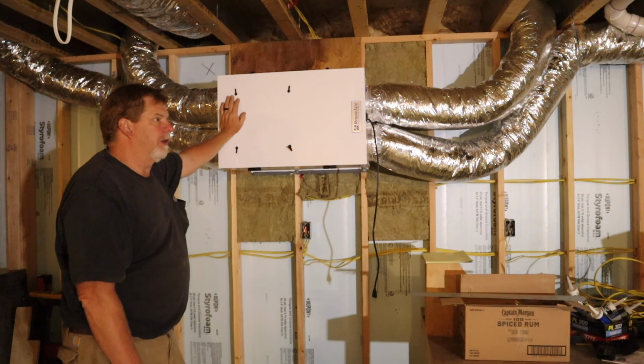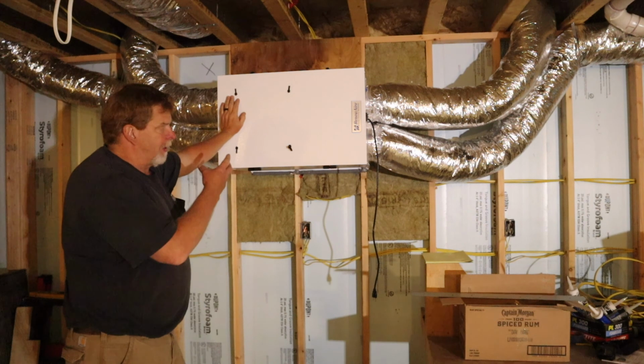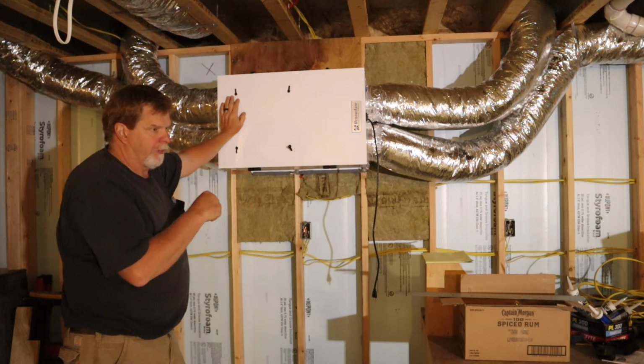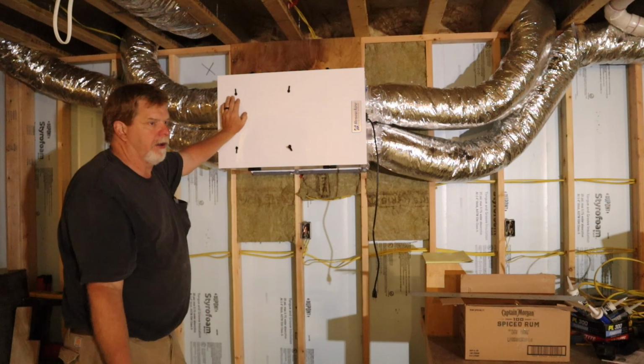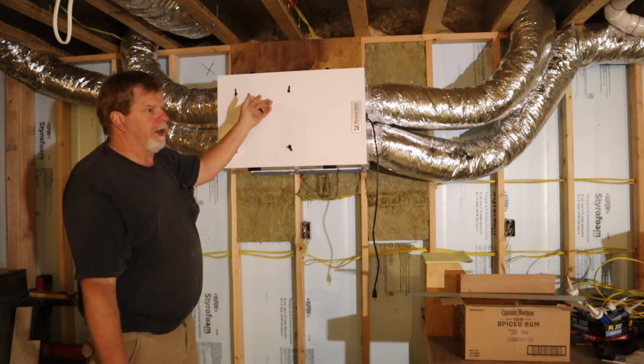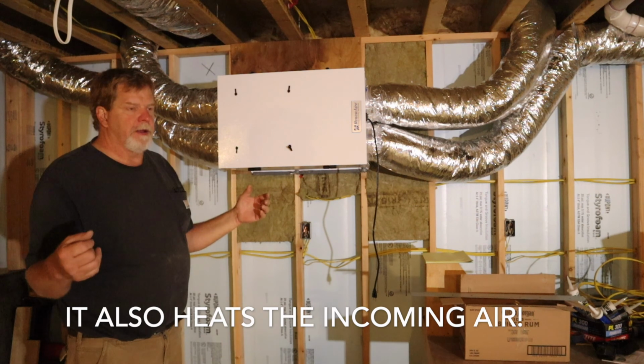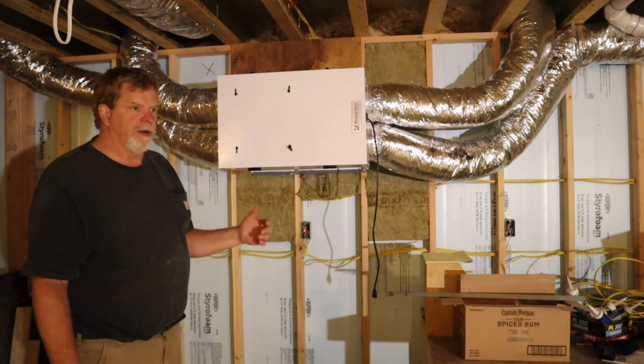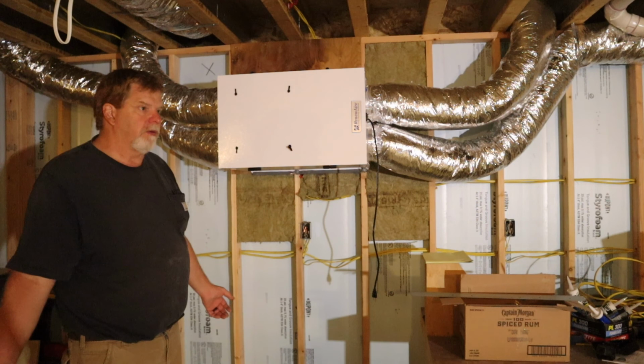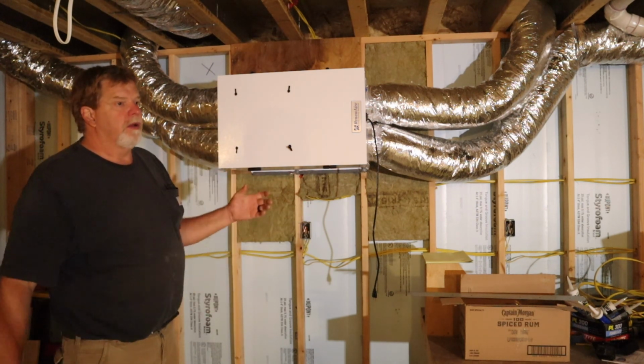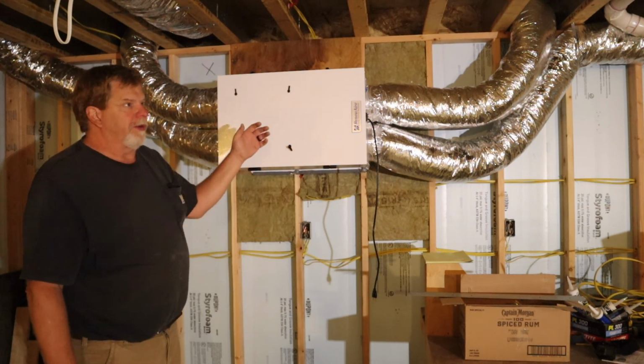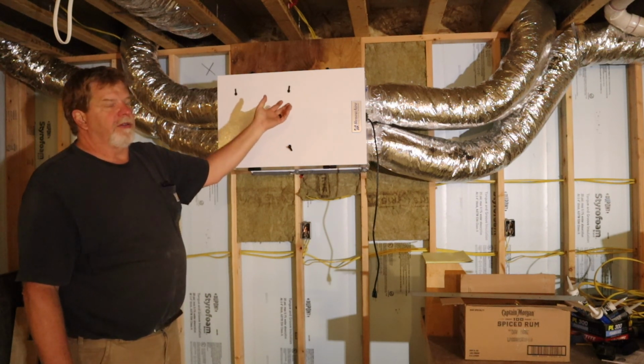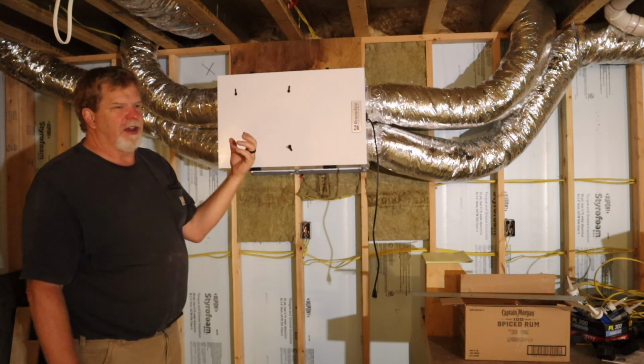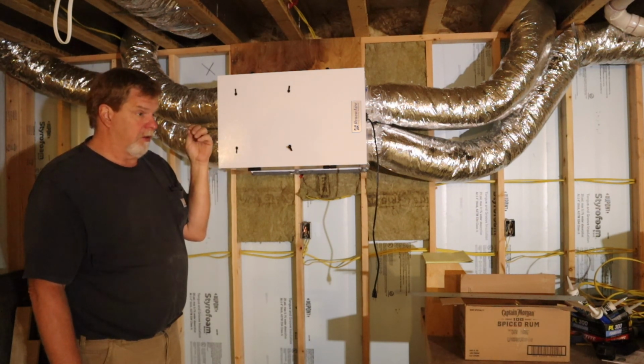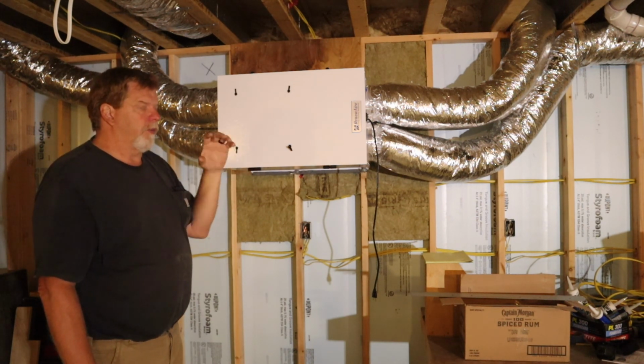He also recommended, for the hood vent, that I have another box similar to this. It's just going to exchange air - it's called a makeup air kit. It's going to pull in air from the outside because my hood vent has a 400 CFM fan, so when that hood vent goes on, it's going to pull a lot of air out of the house. I didn't want to tie it into the ERV because the air going in there is greasy, cooking air, and really humid.